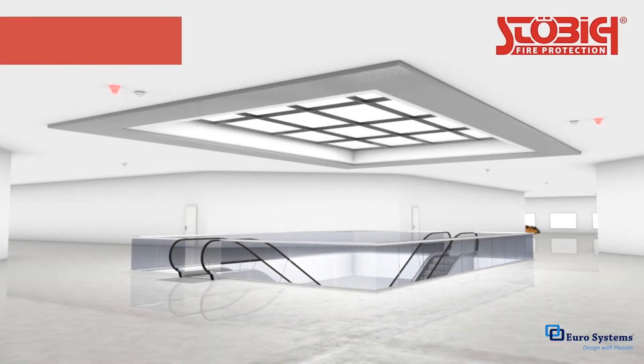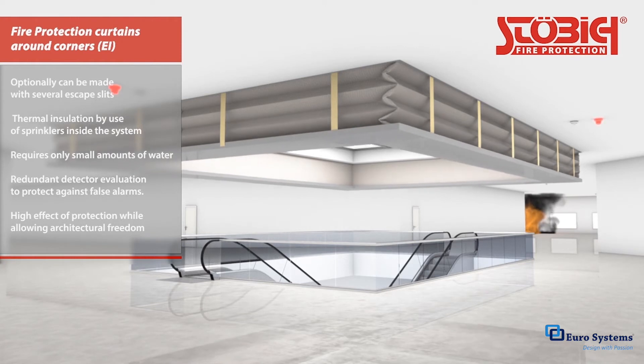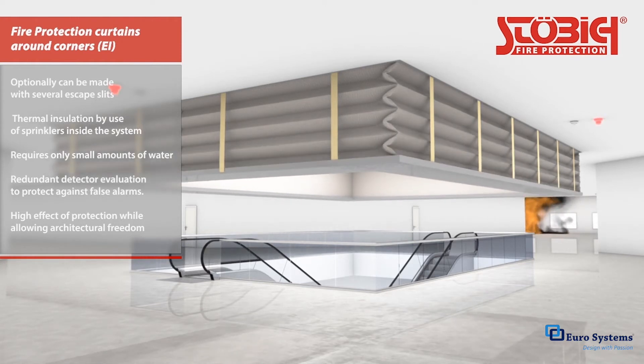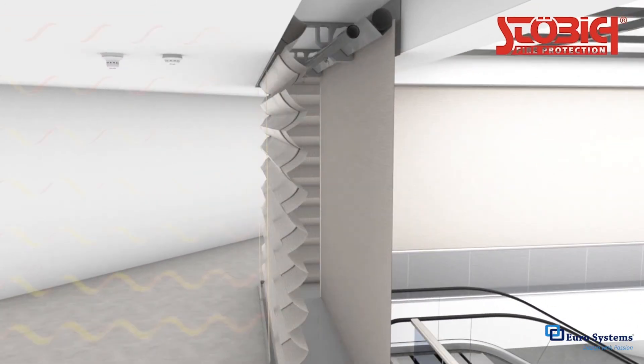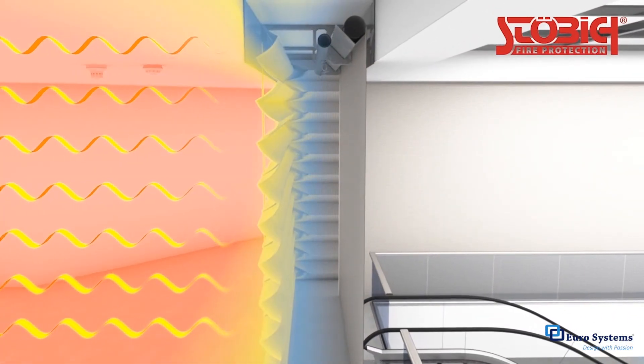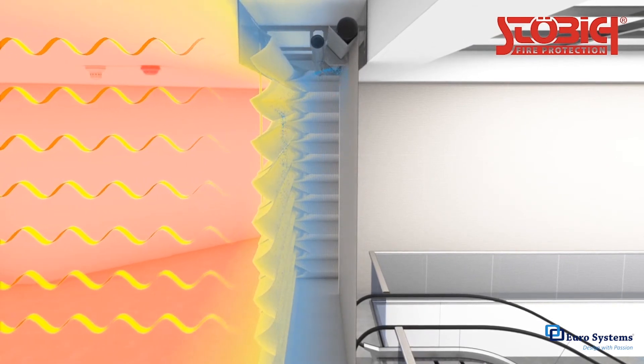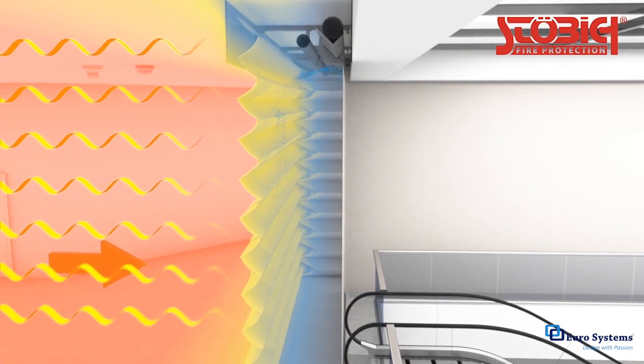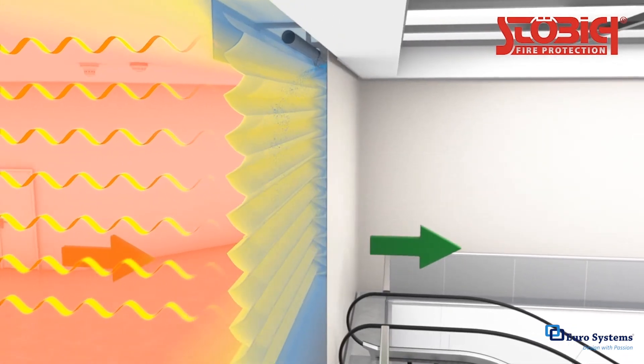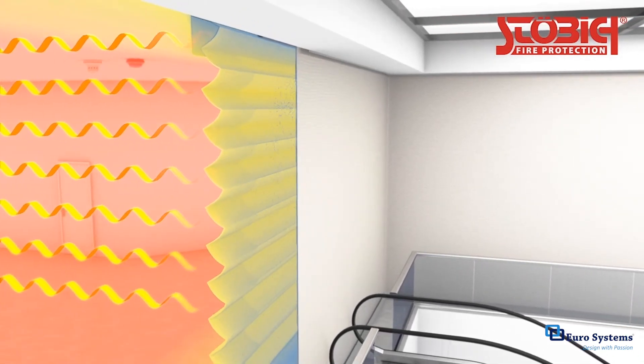A design advancement of the folding curtains around corners is the implementation as a thermal insulating system. The EI-120 protection target is achieved through a combination of folding and rolling technology. The outermost side of the system includes fabric that folds out, just like a standard system. The inner side has a second fabric that unrolls from a tube. If cooling is necessary, sprinklers can be placed in the space between the two fabrics. Optionally, the system can even be equipped with one or more escape or passage slits.